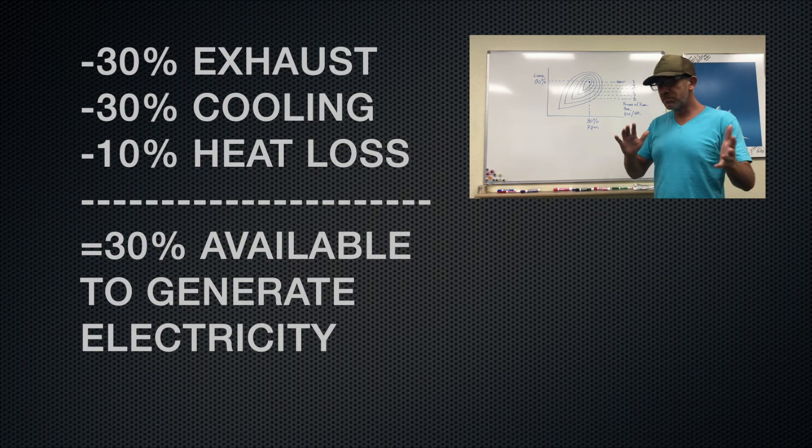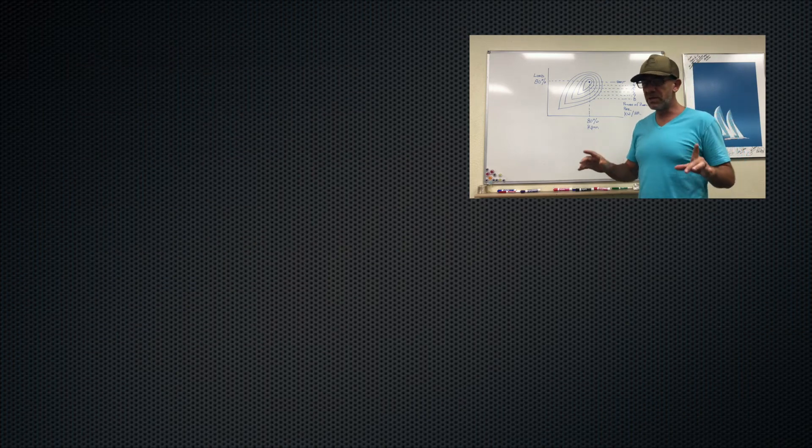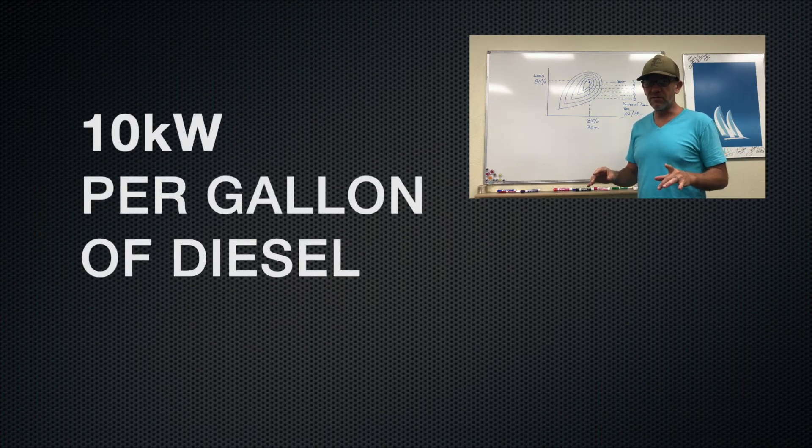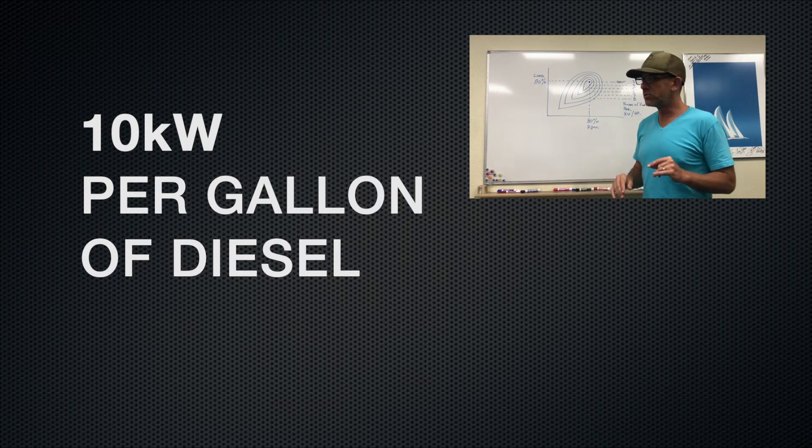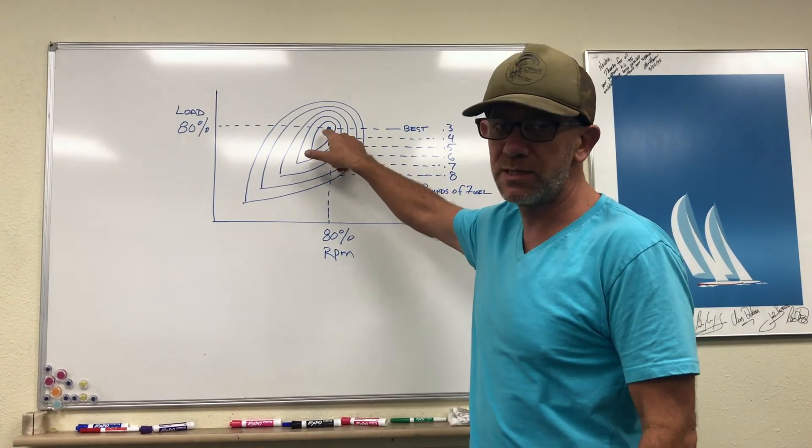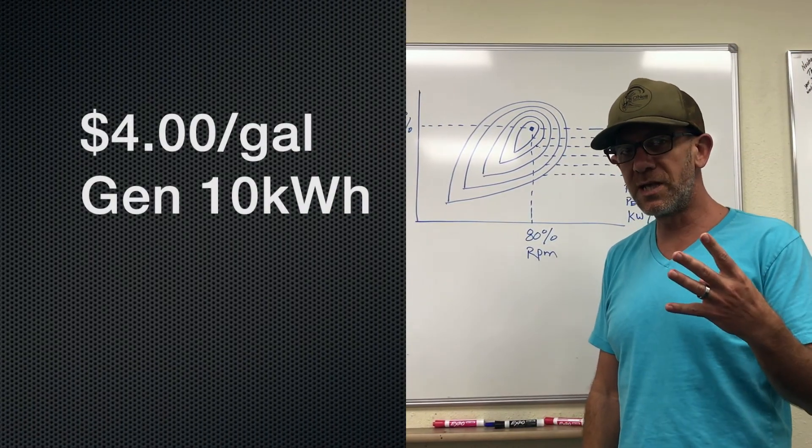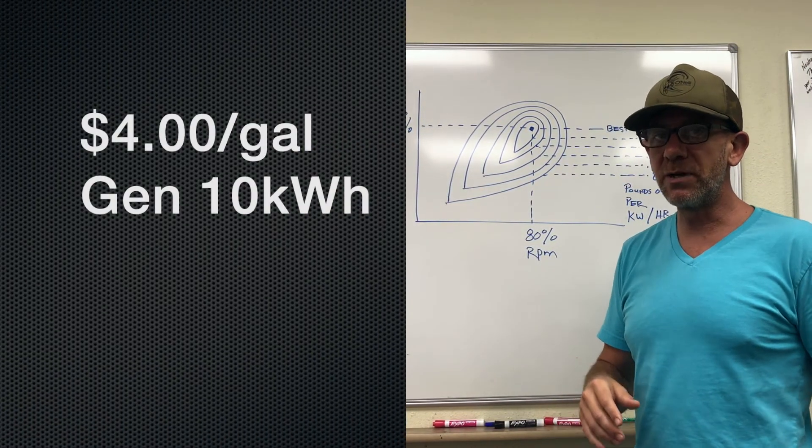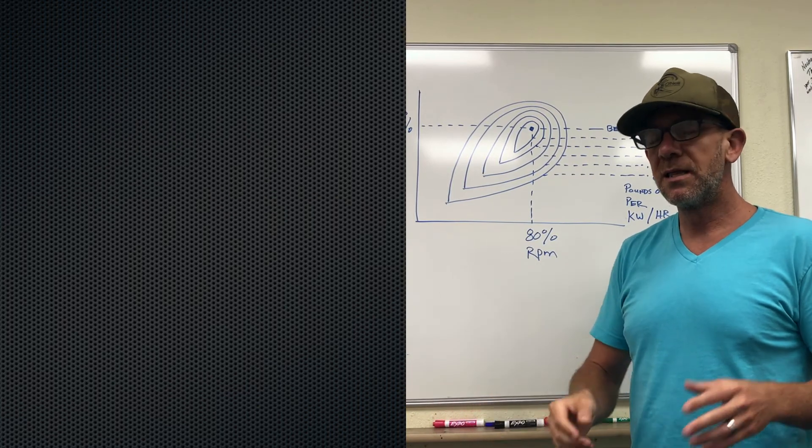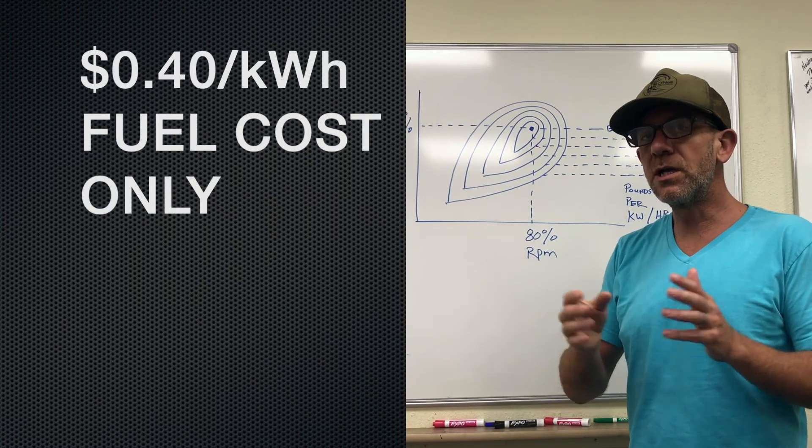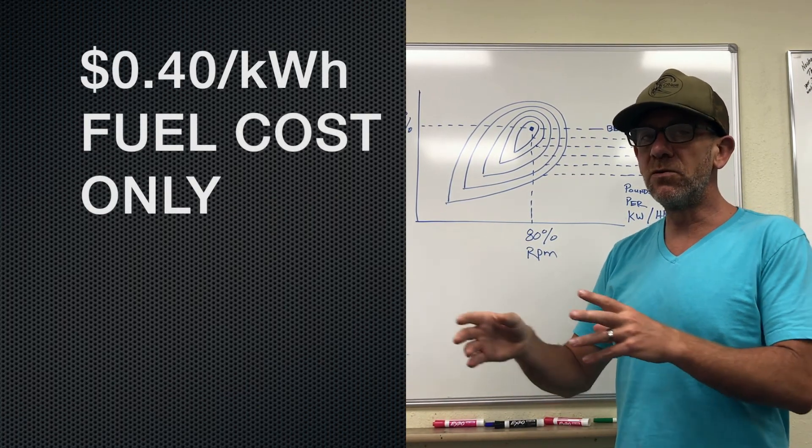So what you're left with is 30% of the available energy in that 130,000 BTUs that's available to generate electricity. Let's just say, to keep numbers round, that ends up being about 10 kilowatts of power that you have available. And that's what you're generating if you are running right at the sweet spot. So if you're buying the fuel for $4 a gallon and you're able to generate 10 kilowatts of power, that's 40 cents per kilowatt just in fuel cost.